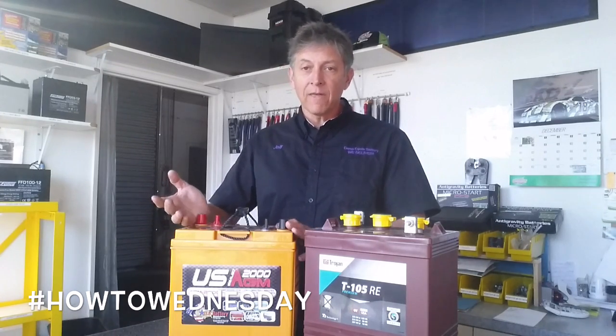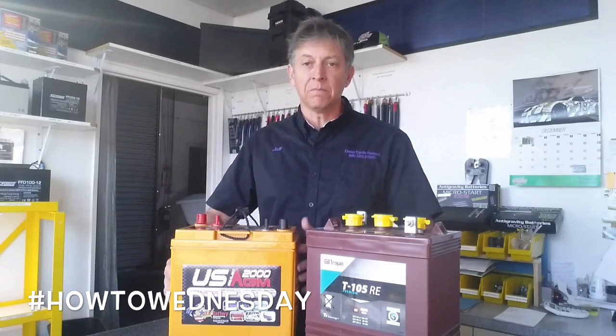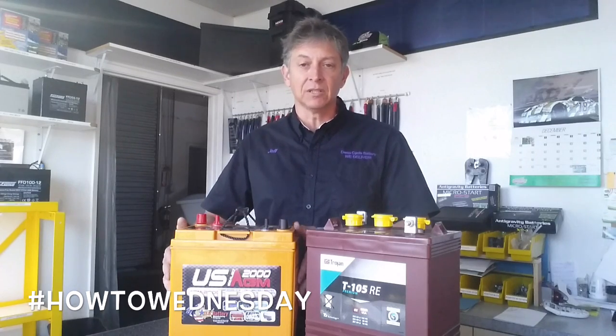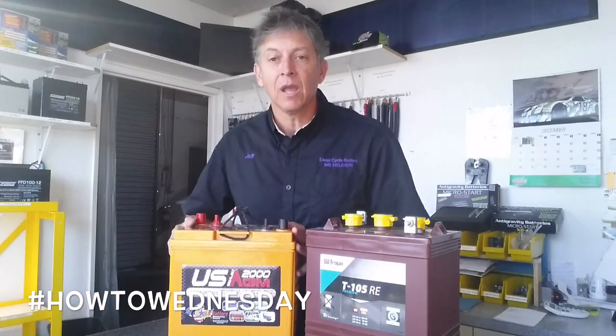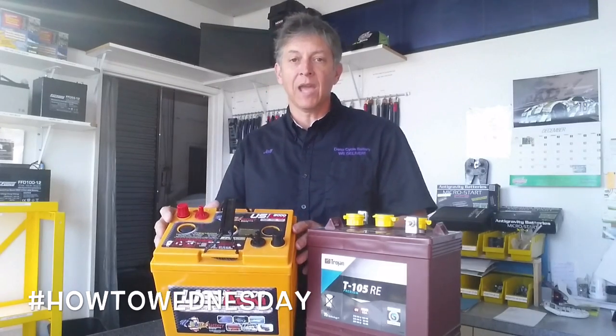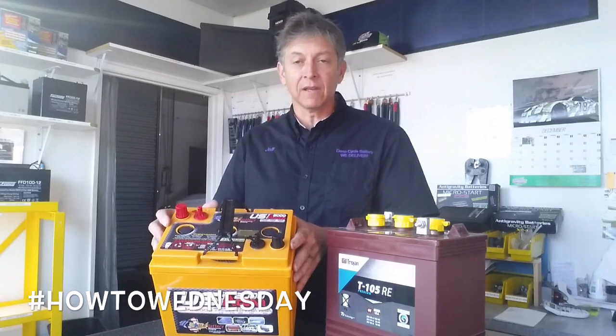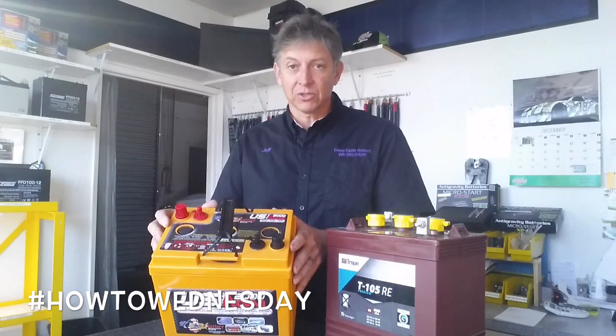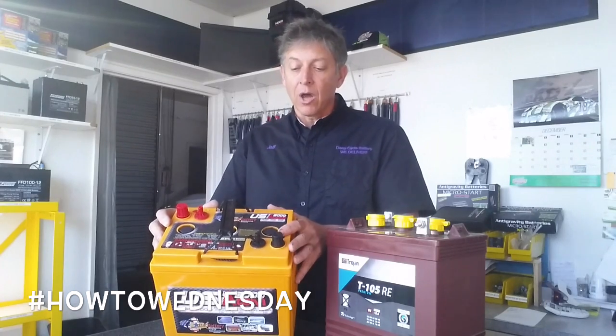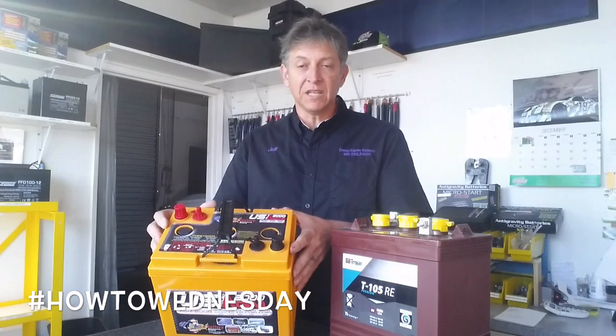We know that's available, but we also know we don't want to discharge a battery down to zero — it's not good for the batteries to completely discharge them. So take the 210 amp hours and divide by 2. That gives you half the battery's capacity, so we only discharge at 50% of the battery's capacity. That gives you 105 amp hours — we can safely stay at 50% or above depth of discharge (DoD).